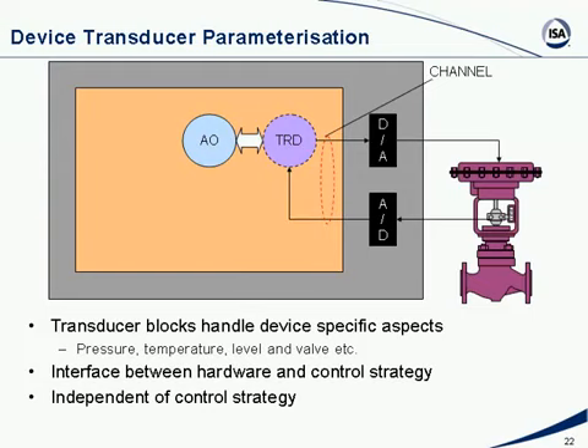Device configuration, or parameterization as we sometimes call it, is done primarily in the so-called transducer blocks. Each device has one resource block, where you get all the information about the device, such as who the manufacturer is, the overall health of the device, model, version, etc. The transducer block is where you configure the sensors and the actuators. Depending on the device type, you will have a different transducer block. A pressure transmitter has a pressure transducer block. A temperature transmitter has a temperature transducer block. A valve positioner has a positioner transducer block.